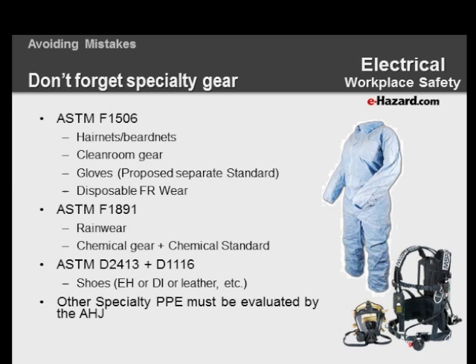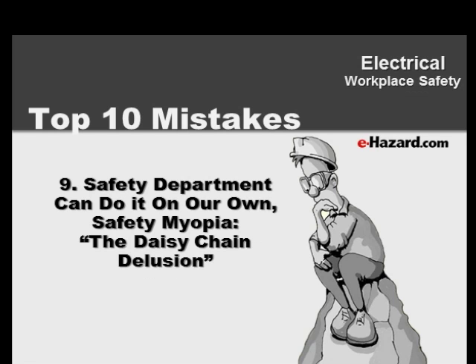Other specialty PPE needs to be evaluated by your AHJ. Maybe you've got an SCBA that's worn periodically. I recommend for arc flash getting a firefighter's type SCBA if it could be exposed to an arc flash. Thinking this through can save you headaches in the long run when specialty equipment for arc flash jobs also involves other hazards.